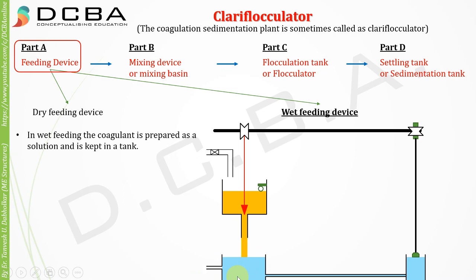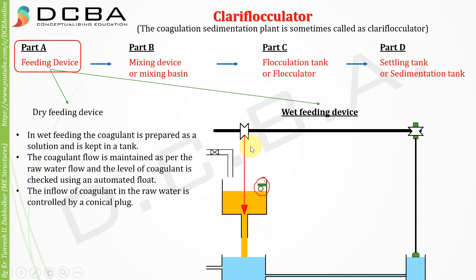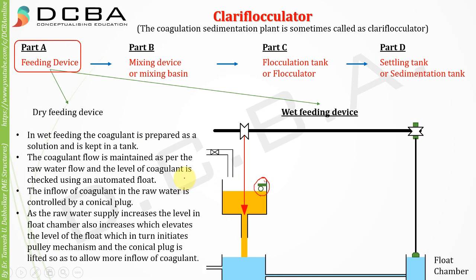In wet feeding, the coagulant is prepared as a solution and kept in a tank. The coagulant flow is maintained as per the raw water flow, and the level of coagulant is checked using an automated float. The inflow of coagulant to the raw water is controlled by a conical plug. As raw water supply increases, the level in the float chamber rises, elevating the float, which initiates the pulley mechanism and lifts the conical plug to allow more coagulant inflow.